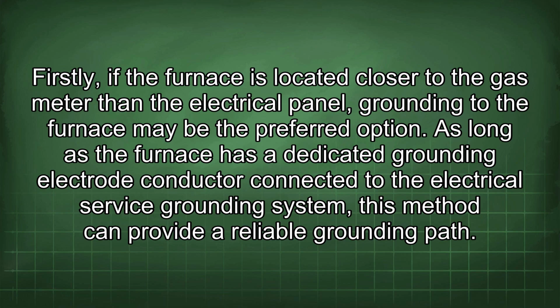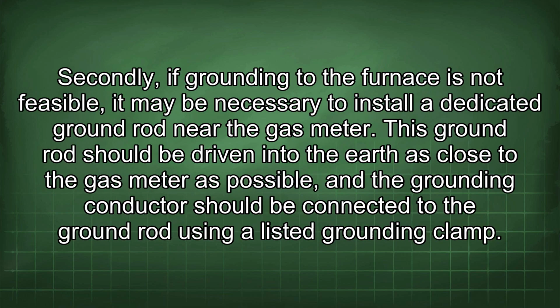Firstly, if the furnace is located closer to the gas meter than the electrical panel, grounding to the furnace may be the preferred option. As long as the furnace has a dedicated grounding electrode conductor connected to the electrical service grounding system, this method can provide a reliable grounding path. Secondly, if grounding to the furnace is not feasible, it may be necessary to install a dedicated ground rod near the gas meter. This ground rod should be driven into the earth as close to the gas meter as possible, and the grounding conductor should be connected to the ground rod using a listed grounding clamp.